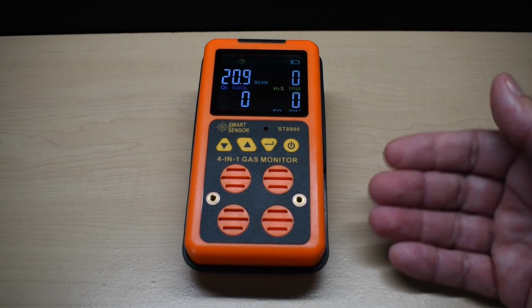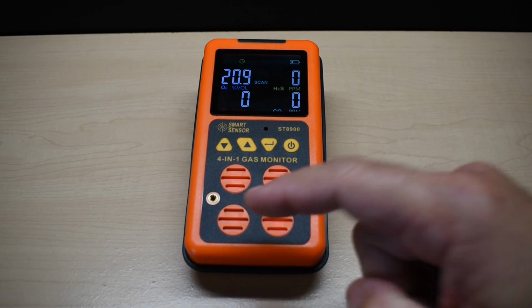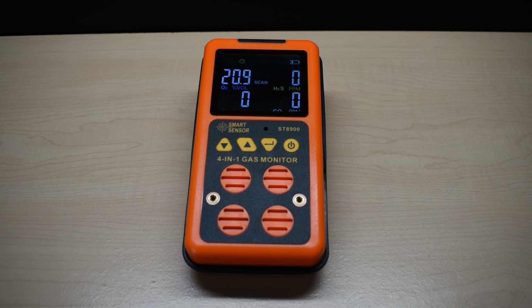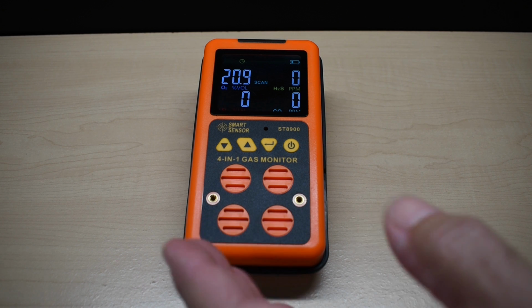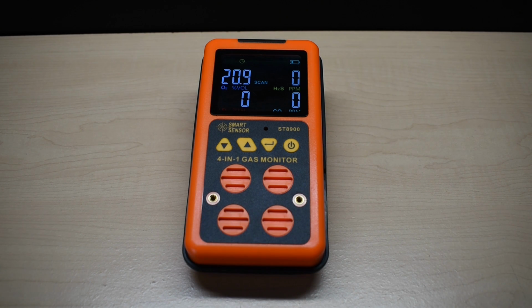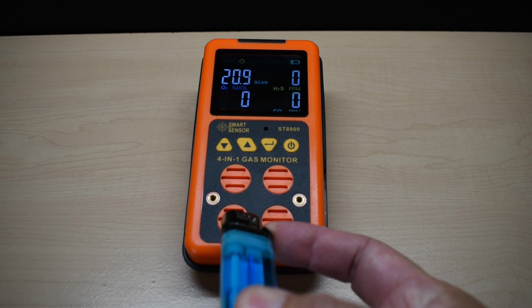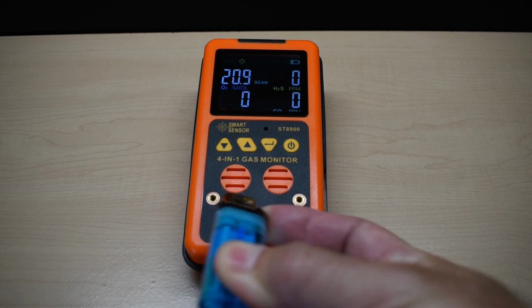Now that you know how easy it is to set this up, let's check out each one of the sensors, make sure they work. The first one's going to be the LEL, that's the lower explosive limit. You can detect methane, natural gas, propane, butane. I'm going to take a little bit of butane from this lighter, place it over the sensor right here.